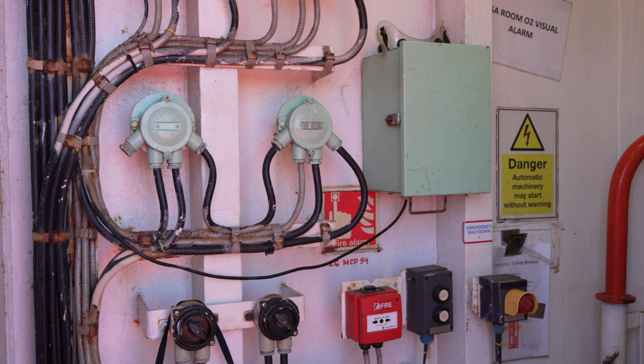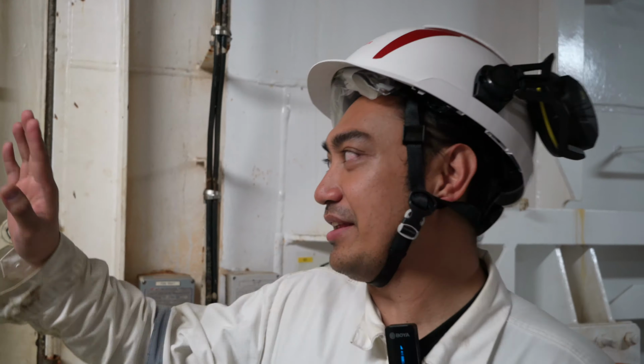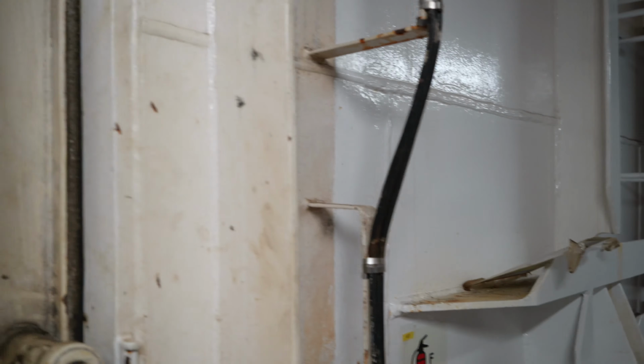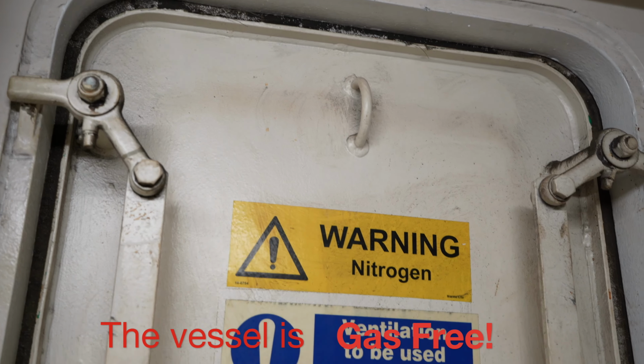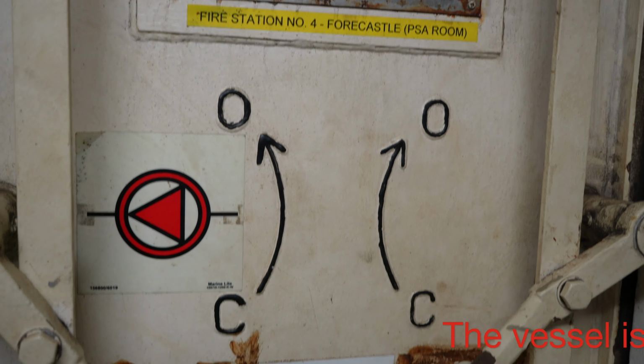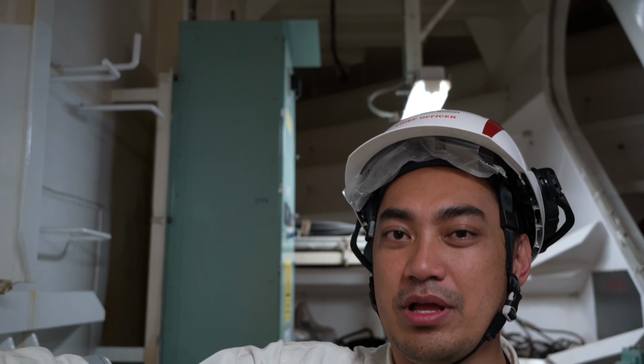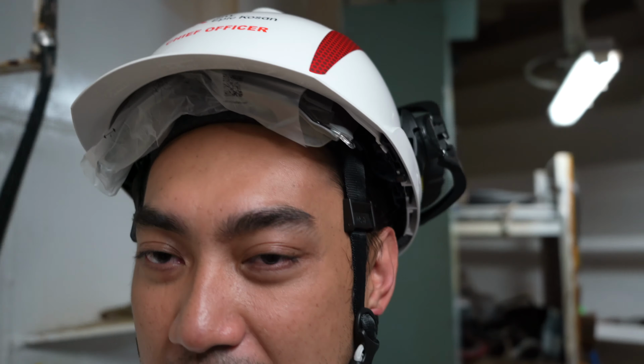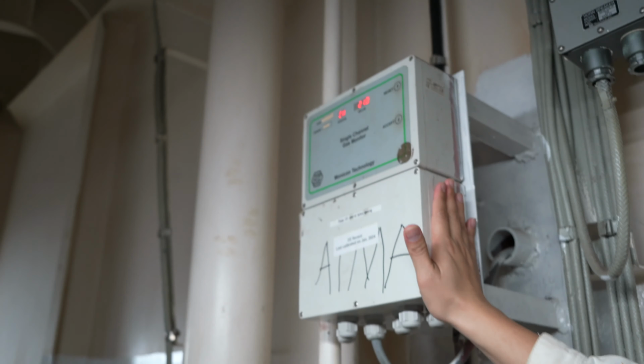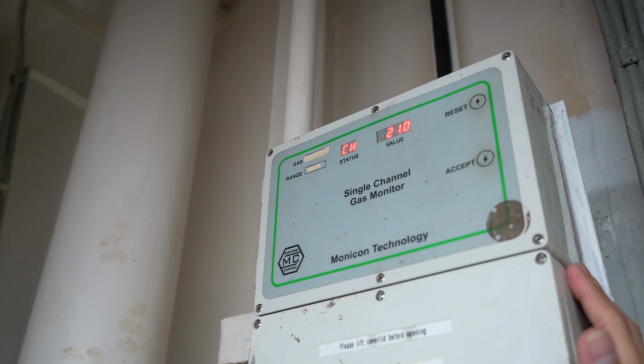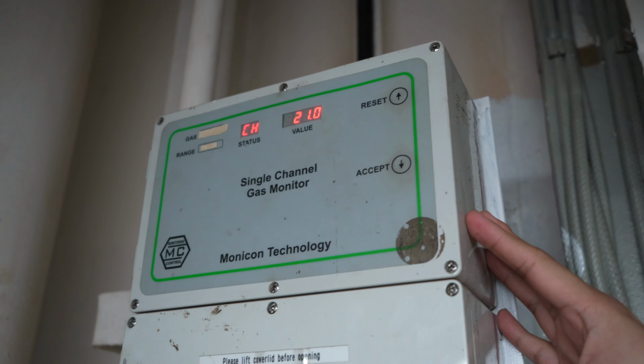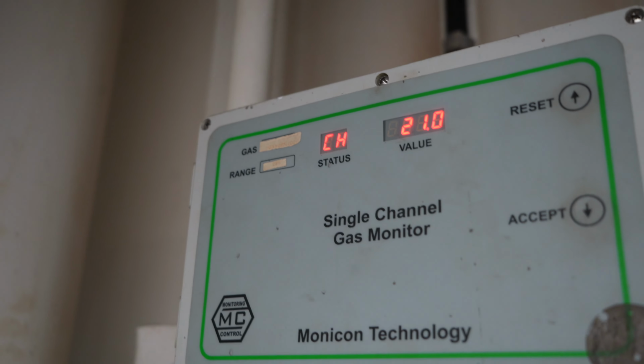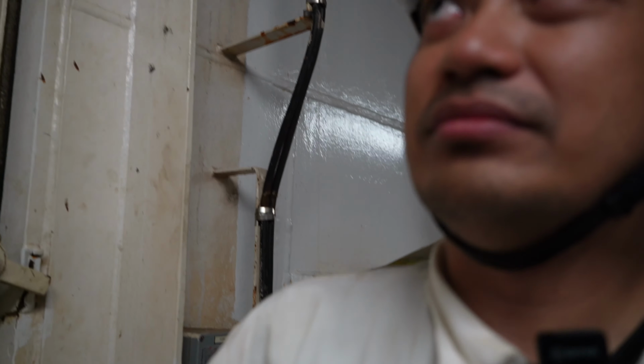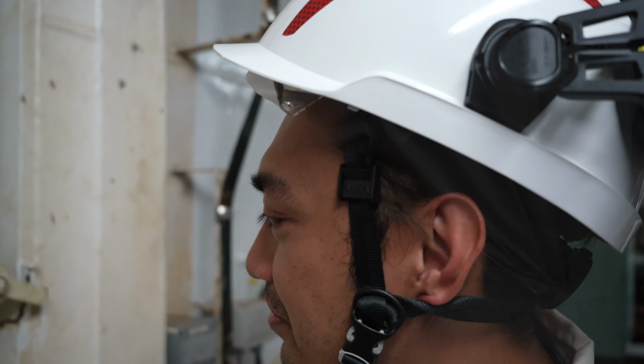Okay, so we can go inside? Yes. This is the entrance of the PSA room. The space we are in now is the bosun store, which is why we also need the supply fan or exhaust for the bosun store. Prior to entering the PSA room, we have a pre-entry oxygen alarm here. Make sure it is within parameters. Now it is 21%, actually about 20.9, so this is an acceptable range. If we are sure, then we can proceed to the PSA room.